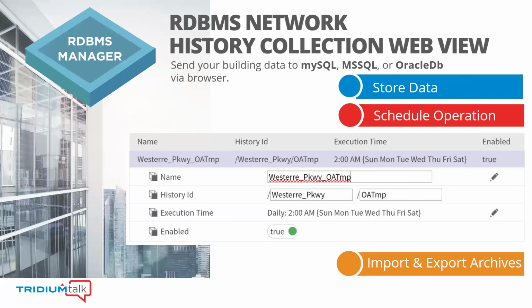Now, what happens over time is that as that database grows and you do a station restart from time to time, when that station restarts, it's got to index every single one of those records. And so best practice, of course, is to export those alarms and histories to a relational database, not only for their safekeeping, but for their instantaneous retrieval if you are using WebChart, for example, within the product.